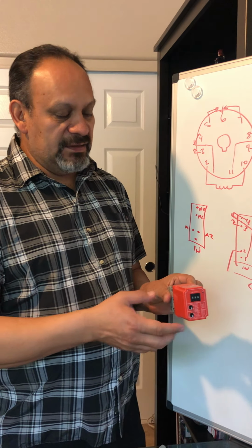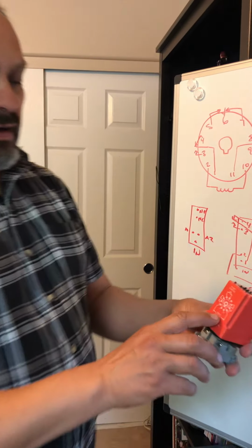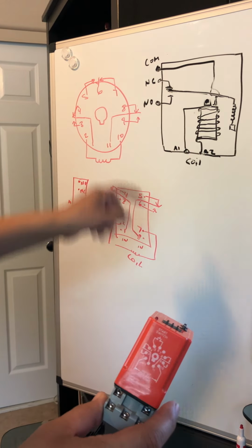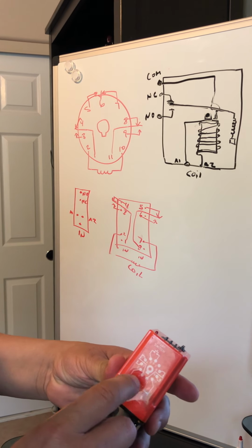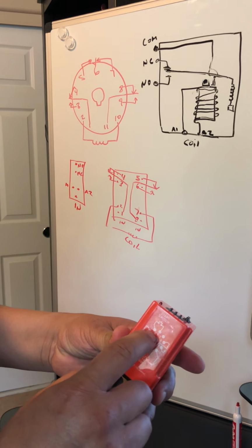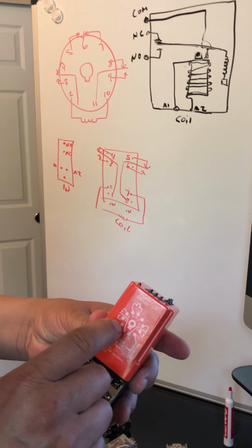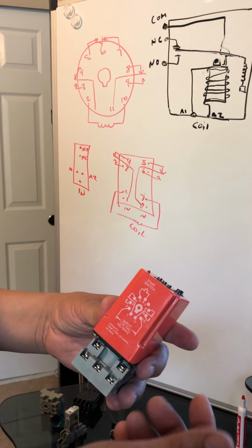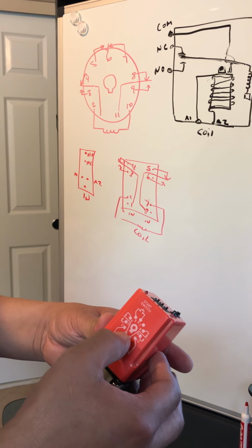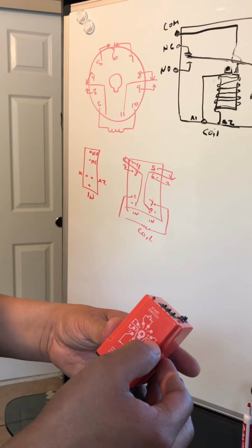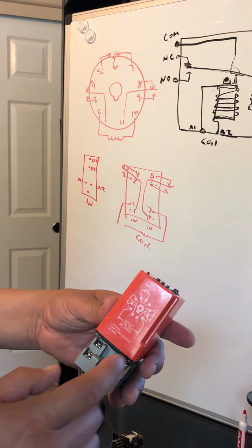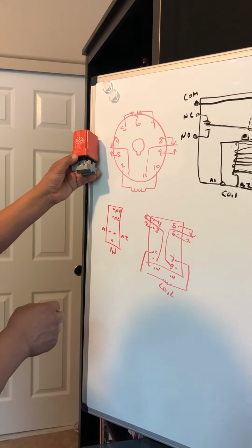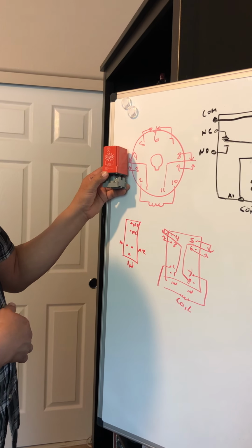Now, again, the same coils, the same thing. If you notice, my coil here is 2 and 10, same as my relay was. 2 and 10 is still my coil, and then you have 1 coming in, closed to 4, open to 3, 6. This one they have for a switch right there, so it's a little bit different. But again, 11 you have normally closed to 8 and open to 9. So it's pretty much the same symbol as this right here, almost exactly the same thing.